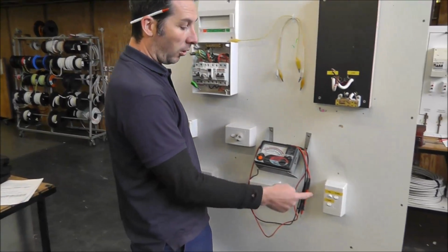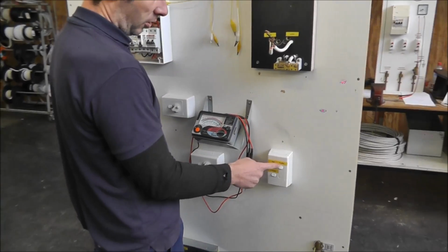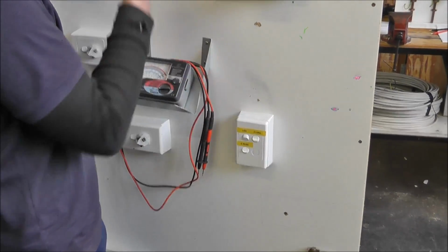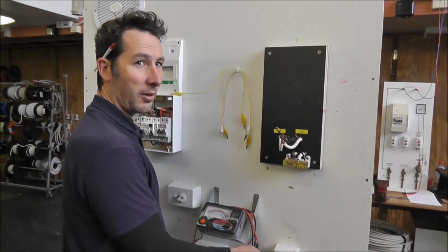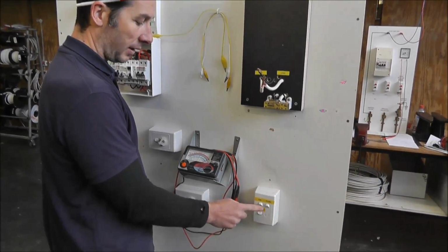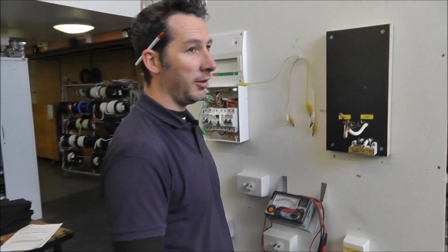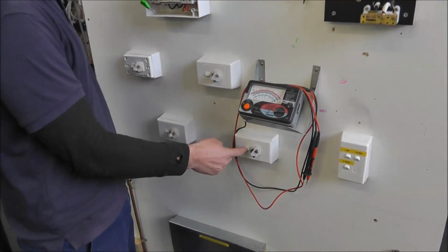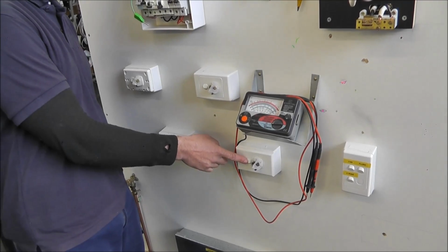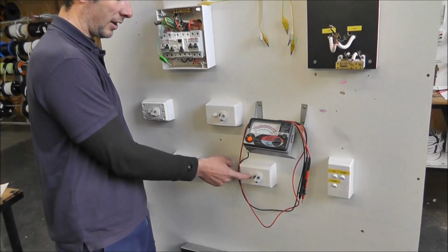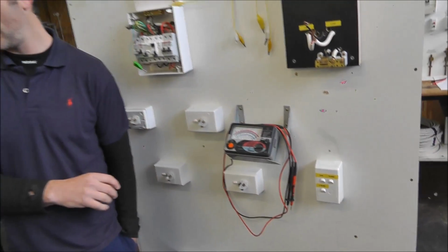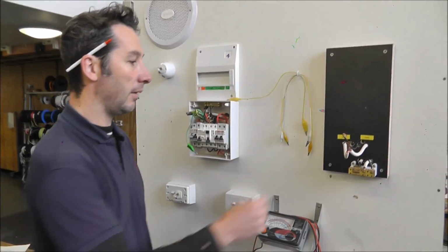If there was a fault, in between this switch here, if there was an active to earth fault in between this switch here and the actual fluoro, and the switch was turned off, would I pick it up? So therefore, it would be fair to say I've got to turn it all on. So I've got to turn all these on. Now while I'm at turning things on, I may as well just turn everything on, in the unlikely event that there would be an active to earth fault after this switch, very unlikely there would be, but let's just turn everything on. Happy with that? She's all going on. Now, another thing to consider.